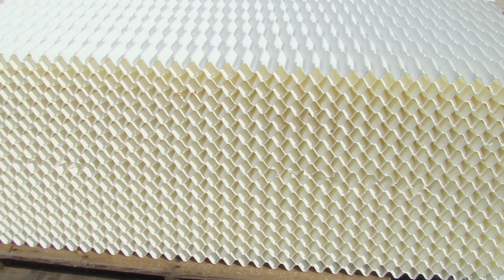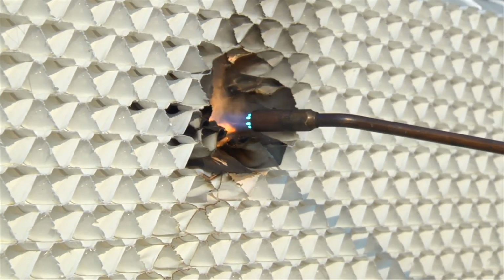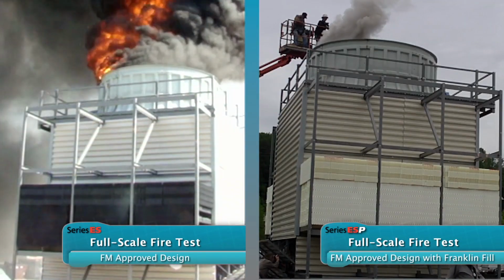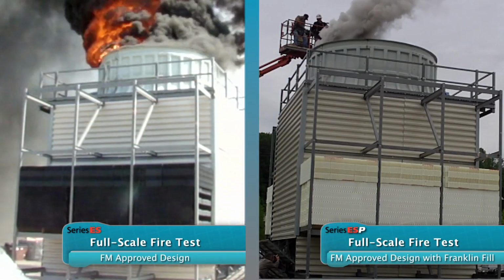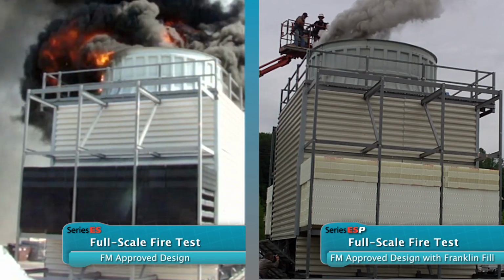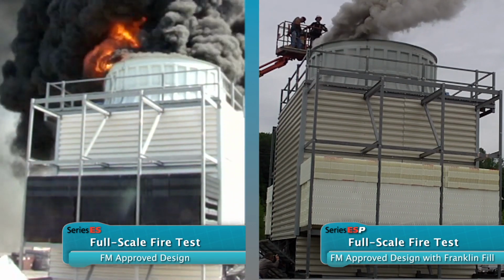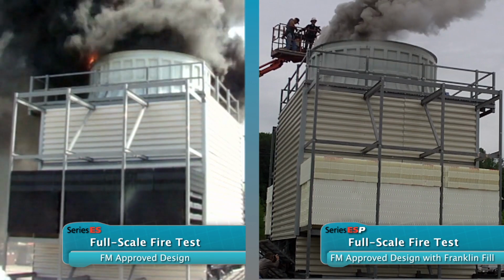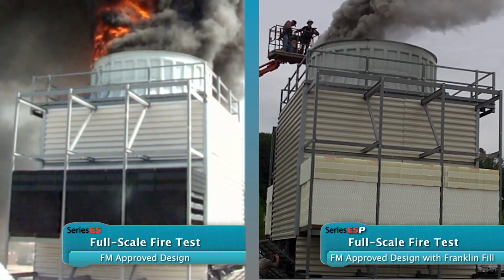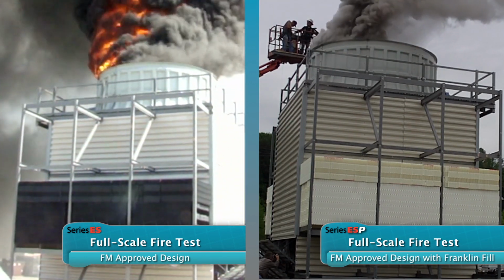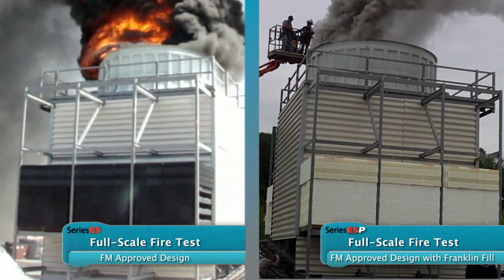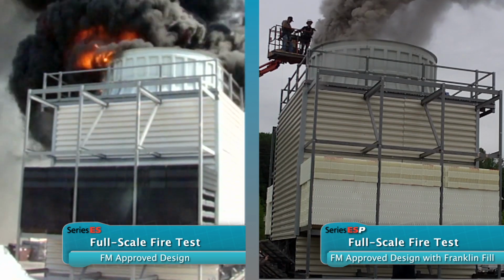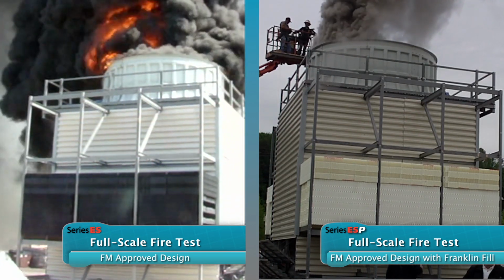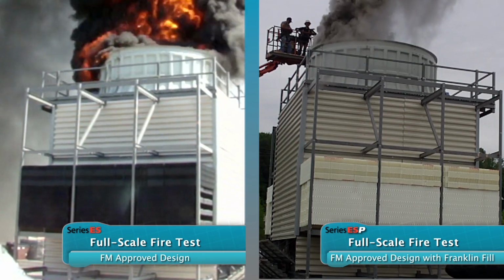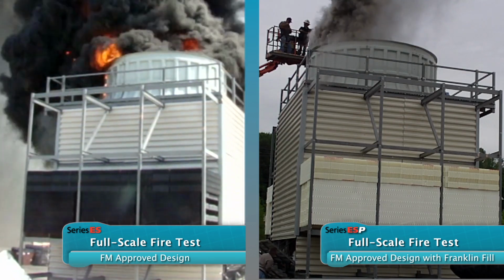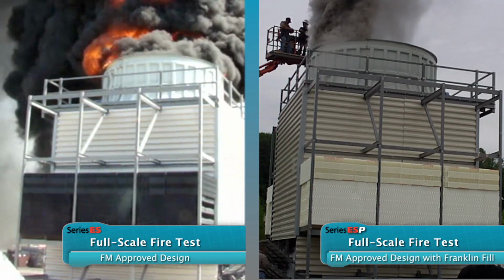Let's revisit Franklin fill and see what makes it so special. This burn test video comparison shows two FM-approved towers. The tower on the left uses normal PVC fill material. As you can see, the fire is raging inside the cooling tower enclosure, but it is contained within the cell. The tower on the right uses Franklin fill. This tower is experiencing a dramatically smaller fire, even with the fire in both towers being ignited with the same fuel source. Now, let's take a look inside the towers.